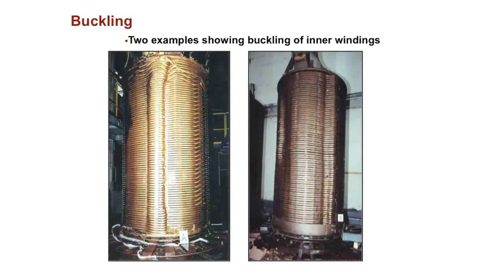It's actually not necessarily a failure. This could happen, and the transformer could live like this for many years, and it could even be just a small dielectric event that fails it. But it's not unusual to take apart a transformer and find some kind of buckling like this in the windings.